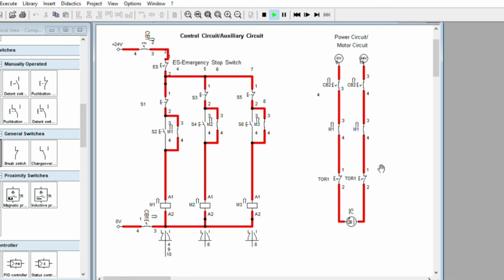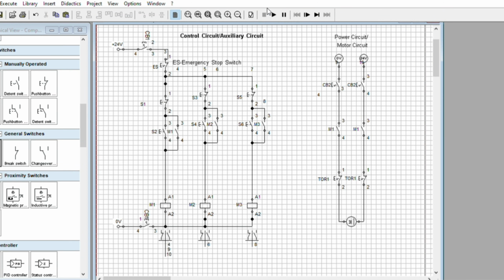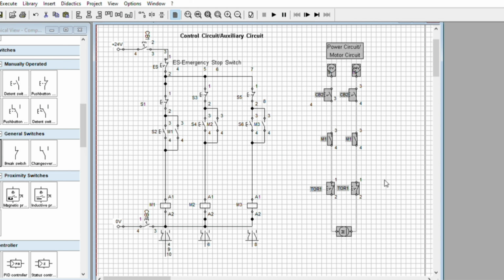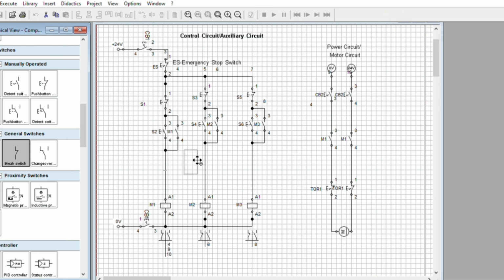If we have 3 motors, or 3 motors are working together, this is not the case. If this one is turning on, we are going to interlock this one, or the other way around. So interlock means to turn off a circuit, to break a circuit. So that means we are going to use normally close contact. Normally close contact. Interlock the two contactors.